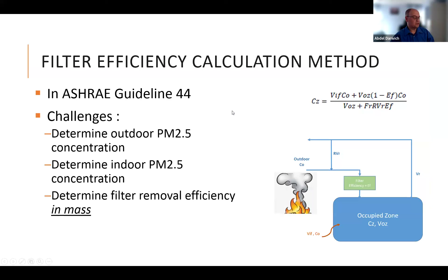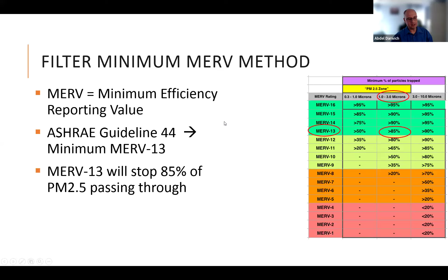filters are usually rated on a MERV, which is the minimum efficiency reporting value. So Guideline 44 recommends a minimum of MERV 13, and MERV 13 stops about 85% of the PM 2.5 passing through. Again, it doesn't mean that 15% will get to the building, because you have some circulation. As the air passes over the filter over and over, it will remove more than that. And most hospitals should have this. So really, MERV 13 should be achievable in any hospital.